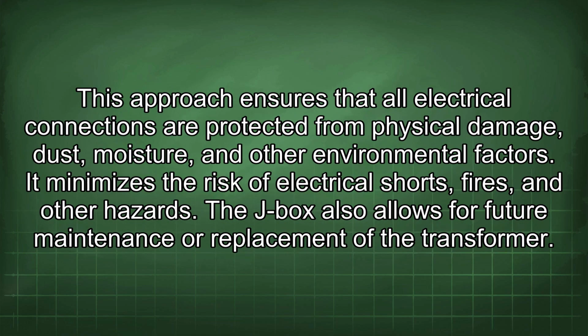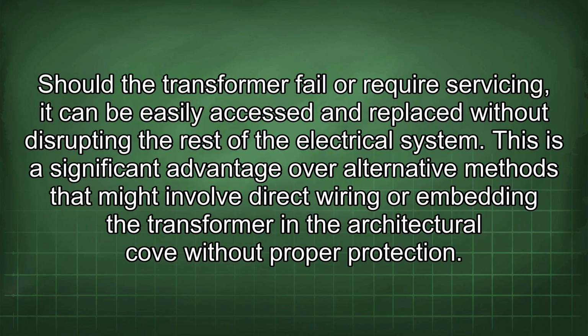This approach ensures that all electrical connections are protected from physical damage, dust, moisture, and other environmental factors. It minimizes the risk of electrical shorts, fires, and other hazards. The J-box also allows for future maintenance or replacement of the transformer. Should the transformer fail or require servicing, it can be easily accessed and replaced without disrupting the rest of the electrical system. This is a significant advantage over alternative methods that might involve direct wiring or embedding the transformer in the architectural cove without proper protection.